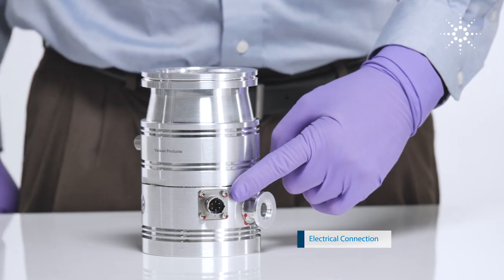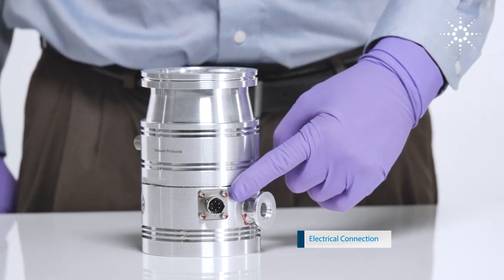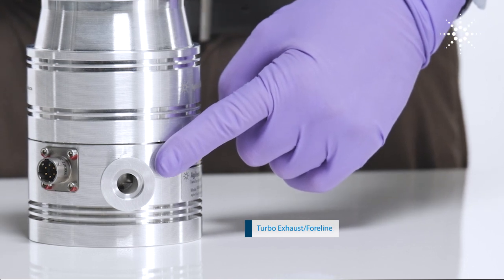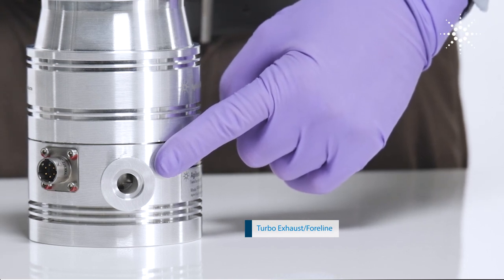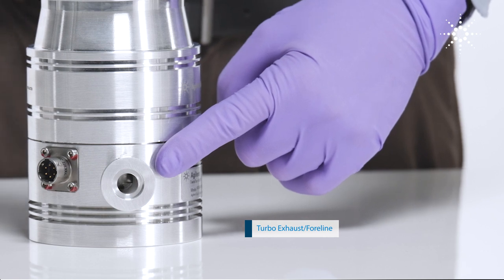The electrical connection here provides power from the turbo's electronic controller to the pump motor. Here is the exhaust of the turbo, also known as the foreline, which will need to be connected to a rough vacuum pump, usually referred to as a backing pump.